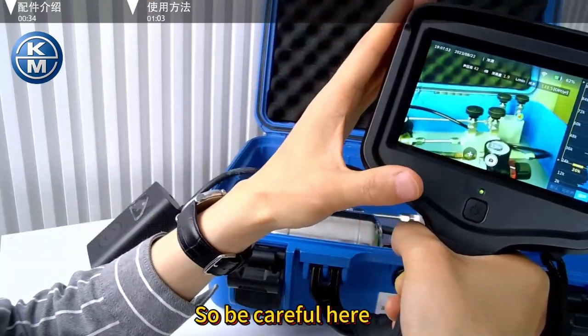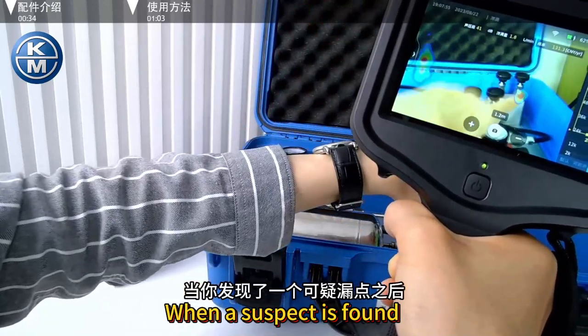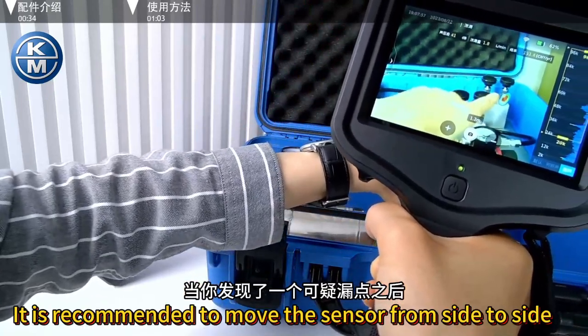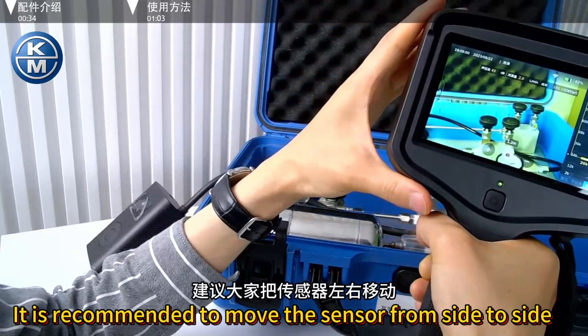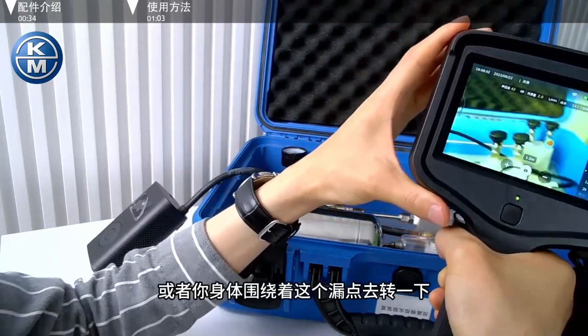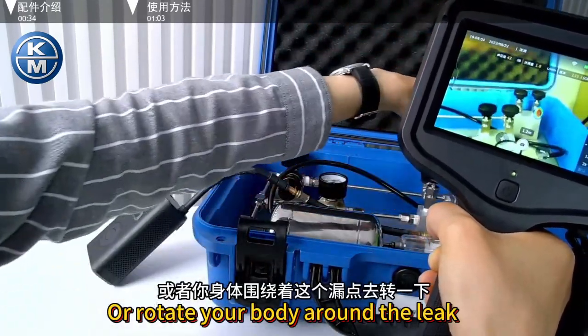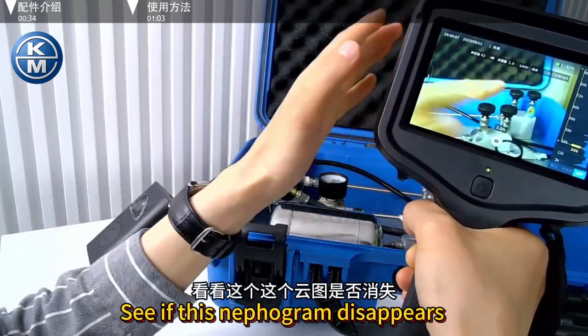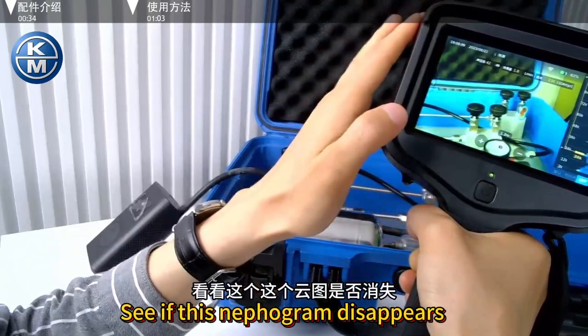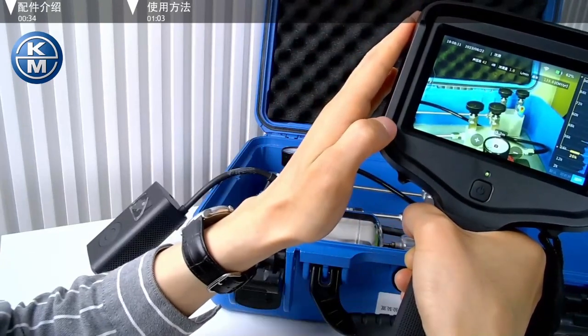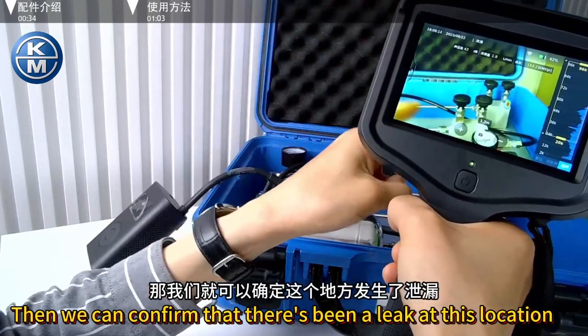So be careful here. When a suspect is found, it is recommended to move the sensor from side to side, or rotate your body around the leak. See if this cloud image disappears. If it still exists, then we can confirm that there's a leak at this location.